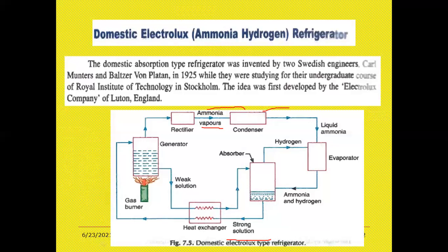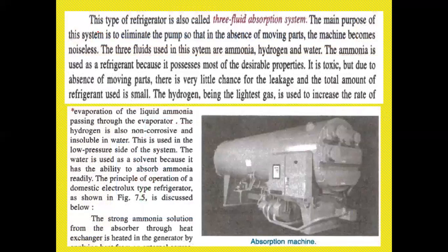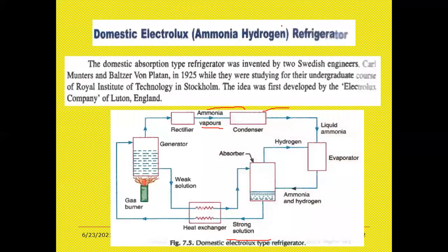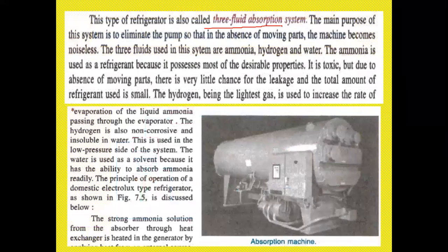converting it into a strong solution by passing it into the heat exchanger. In this heat exchanger the weak solution goes back into this chamber and the strong solution goes into this chamber, right? In this way the Electrolux or ammonia hydrogen refrigerator will operate. See here, this type of refrigerator is also called a three fluid absorption system. So finally we have two other names for this ammonia hydrogen refrigerator. The first one is Electrolux, the domestic Electrolux refrigerator, or three fluid absorption refrigerator.